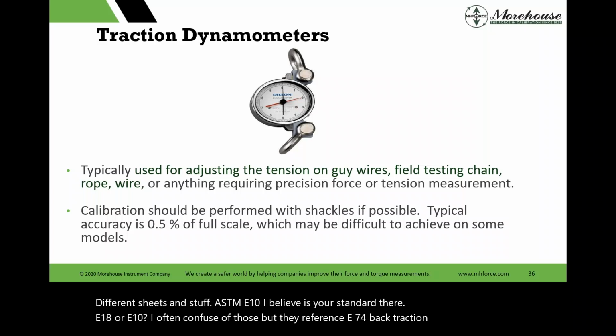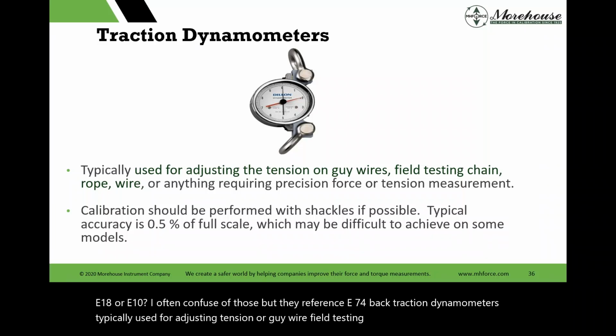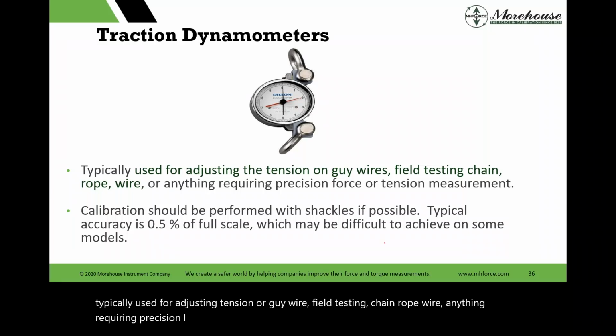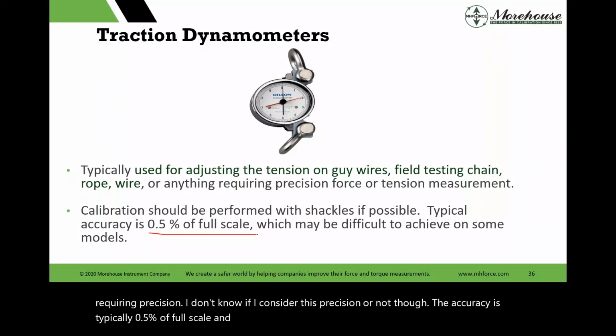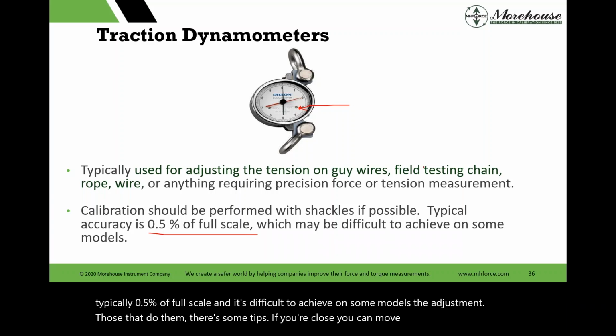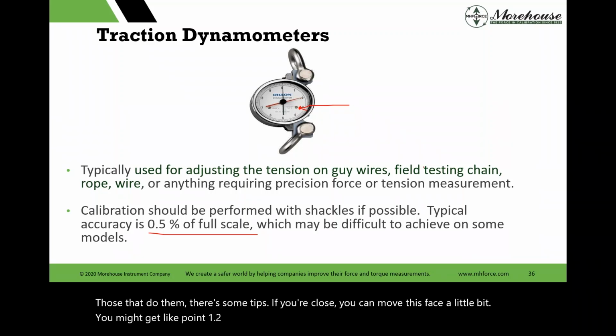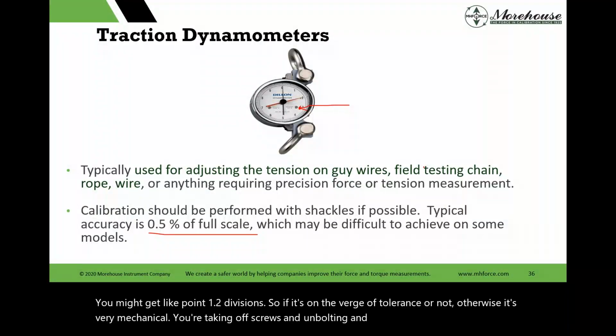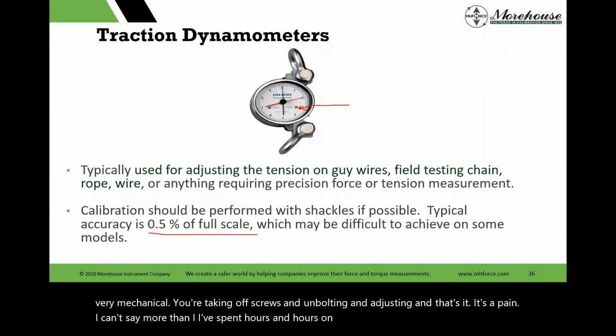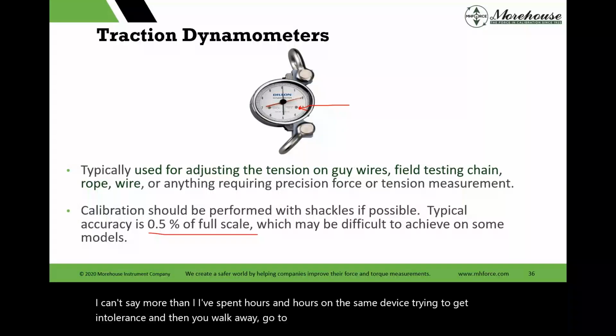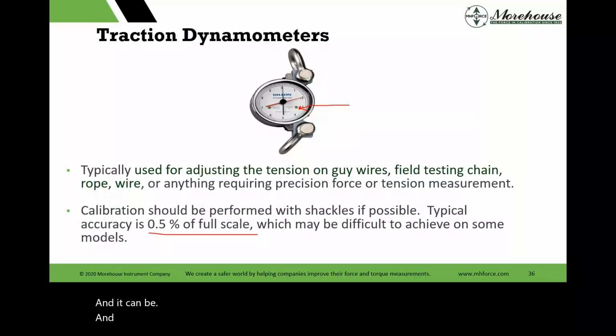Traction dynamometers are typically used for adjusting tension or guy wire, field testing chain, rope, wire, anything requiring precision. I don't know if I consider this precision or not, though the accuracy is typically 0.5% of full scale, and it's difficult to achieve on some models. For the adjustment, for those that do them, there's some tips. If you're close, you can move this face a little bit. You might get like 0.1, 0.2 divisions. So if it's on the verge of tolerance or not, otherwise it's very mechanical. You're taking off screws and unbolting and adjusting, and that's it. It's a pain. I can't say more than I've spent hours and hours on the same device trying to get it in tolerance, and then you walk away, go to lunch, and you come back and you do it again, and magically it's in tolerance. That's only because you warmed it up so much and it needed time to cool down.